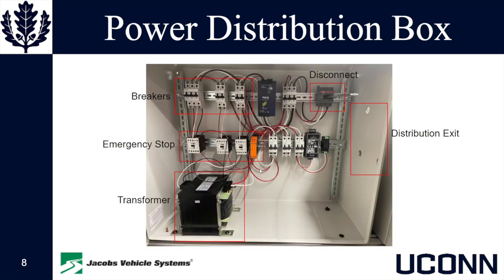Inside the box, the power is distributed and interrupted by a series of circuit breakers. If a short occurs, these devices protect the equipment that is provided power. The emergency stop is operated with controlled magnetic contactors that interrupt the flow of current.